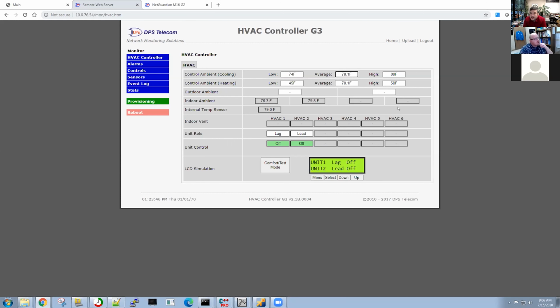The way we're currently handling the string, it goes into that average. And if I remember right, Jesse, I think it triggers on an OR, meaning it's very sensitive - so if any one of the zones is above the high, it's going to kick on, and then it evaluates how it should lead and lag based on the average of all of them. So it's kind of a middle ground, but then it doesn't shut down till they're all happy, till they're all back below the low. That's kind of the way we wrote it originally.